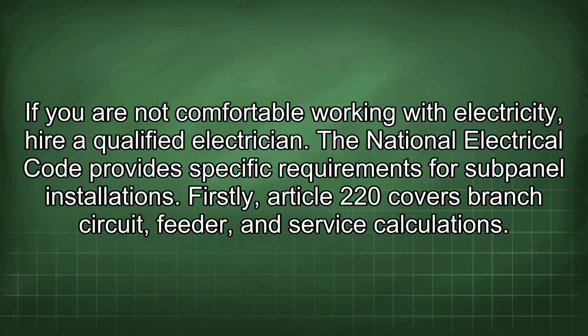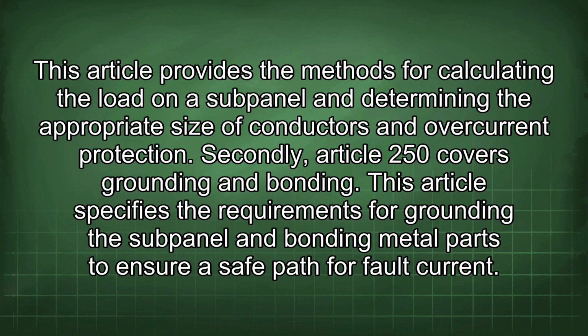The National Electrical Code provides specific requirements for subpanel installations. Firstly, Article 220 covers branch circuit, feeder, and service calculations. This article provides the methods for calculating the load on a subpanel and determining the appropriate size of conductors and overcurrent protection. Secondly, Article 250 covers grounding and bonding.